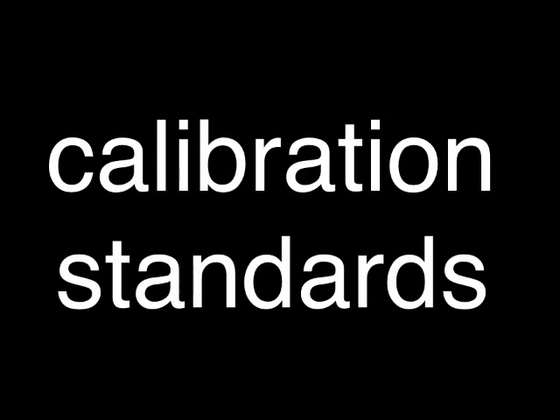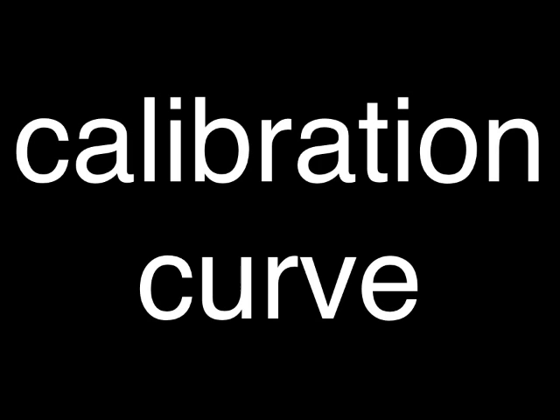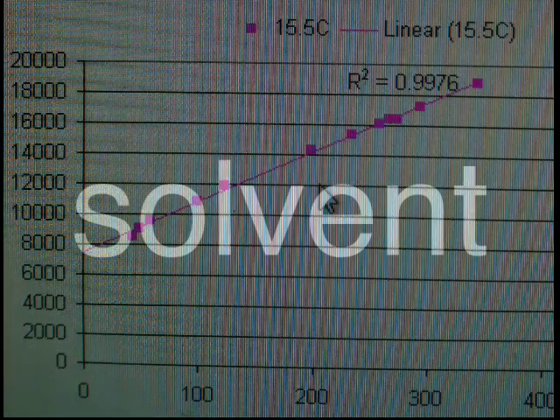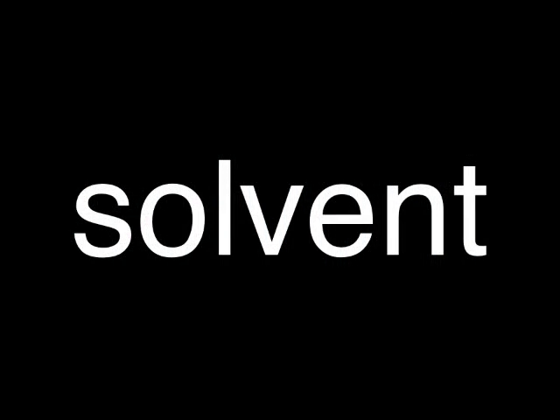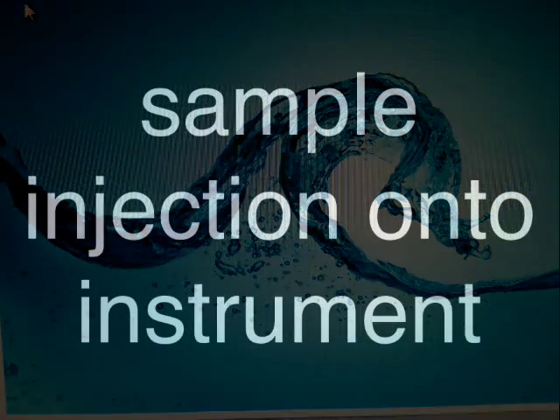Create 7 standards with increasing concentration of the analyte. You will then run these on the instrument and obtain a regression line, also known as a calibration curve. This regression line will then be used to obtain any unknown sample's concentration. Solvent. The most common solvent used is simply water, deionized water.